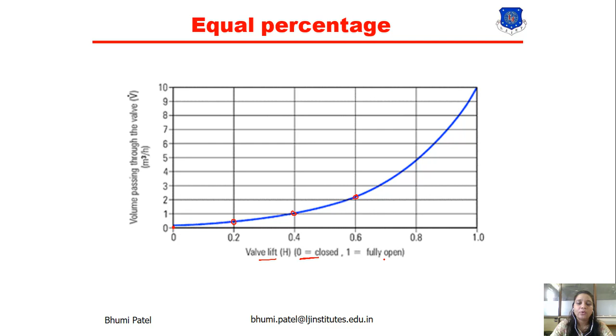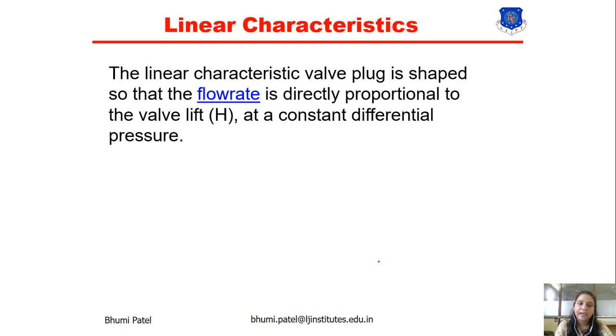Now the linear characteristic. Now what is the linear characteristic? This characteristic provides a linear relationship between the valve position and the flow rate. So in the linear characteristic, the valve plug is shaped so that the flow rate is directly proportional to the valve lift at constant differential pressure. So this is the graph of the valve lift relationship with the volume passing through the valve. So we can get the linear graph.